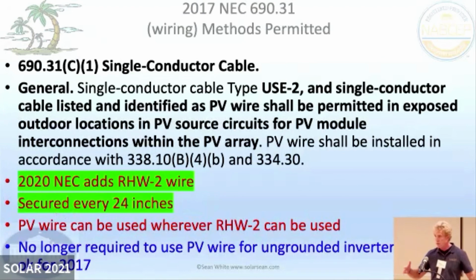And so the width of a solar module is like 38, 39 inches. You can't just have a conductor, even on your ground mount, that's going more than 24 inches. It makes things a little bit more difficult because it used to be 4.5 feet. Yeah, we're going from 4.5 feet to 24 inches. So we'll see, there might be some feedback on that, and they might change it back after a while.